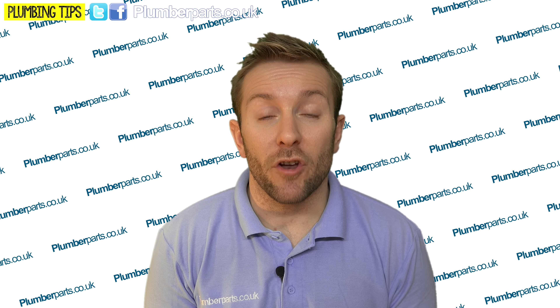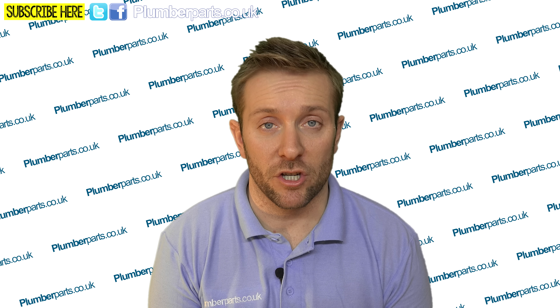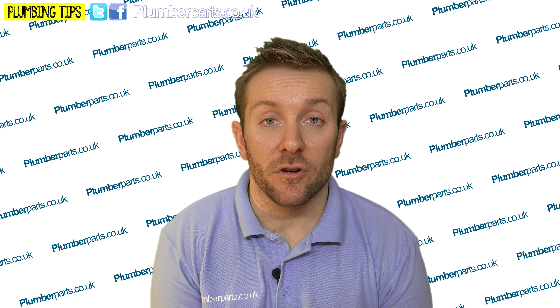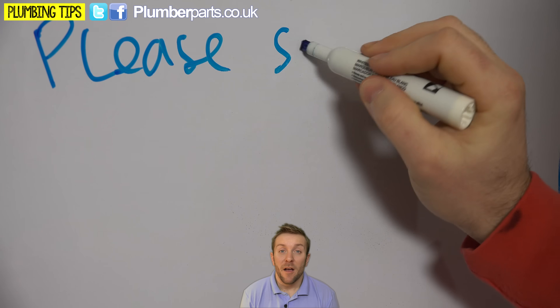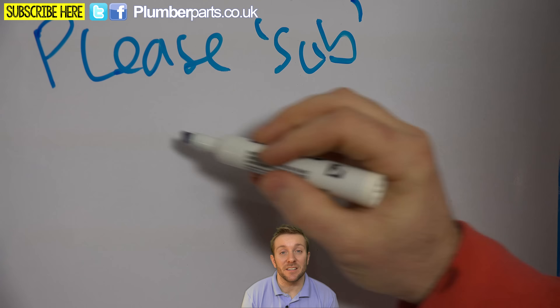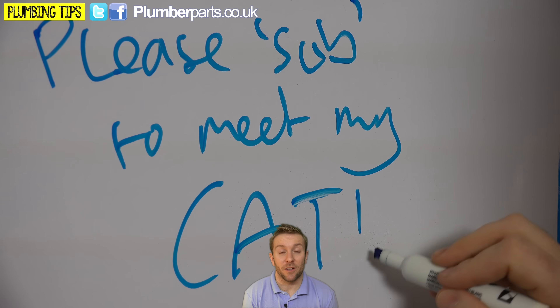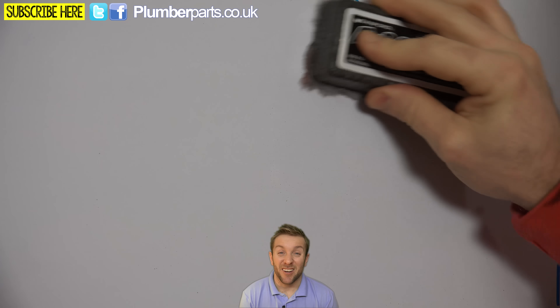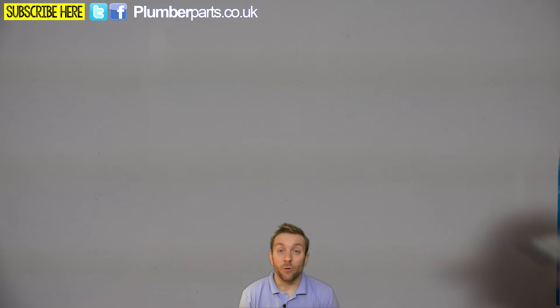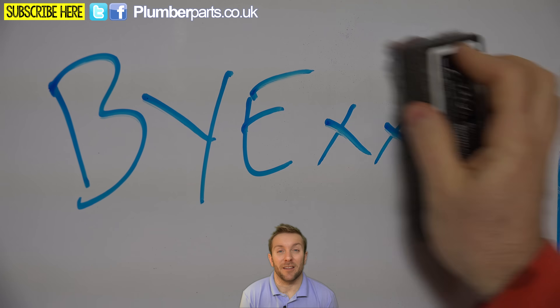So there we go — I hope this video has given you a better idea about the problems you can have with your pressurized heating system and why you're getting a pressure drop. The most common causes are the expansion vessel, the pressure relief pipe, or a leak on your system. It's always a good idea to top up the inhibitor if you're not sure, and periodically ask your plumber to do a health check — drain the whole heating system out, fill it all up again, pop a couple of tubs of inhibitor in there. Also ask them to bang a magnetic filter on the return to the boiler, and you'll really halve any problems you might have from running the heating system.